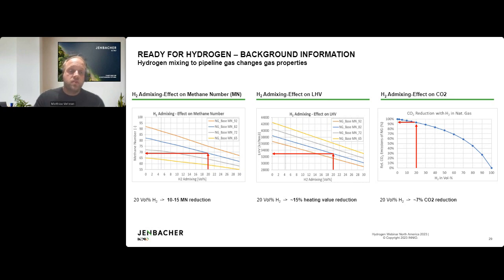At 20% admixing, we typically see a 10 to 15 point reduction in the methane number. Heating value is also reduced. Hydrogen has a superior gravimetric heating value, but on a volumetric basis, because of its very low density, the heating value is actually fairly low. So as we add hydrogen to the natural gas stream, the lower heating value of the fuel is reduced. This can have consequences for the layout of the gas train delivering the mixture to the engine.